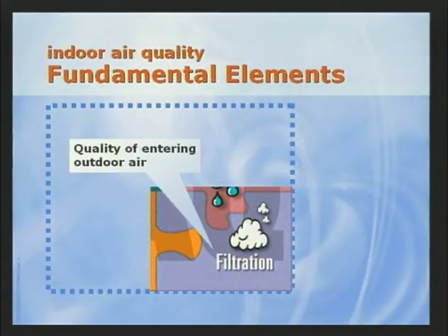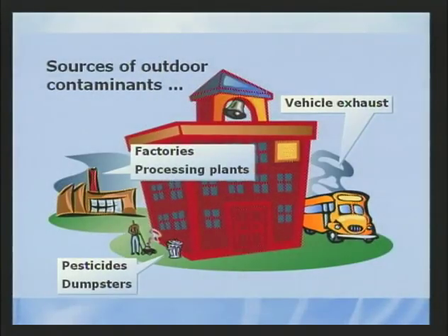Now let's take a moment to look at the ventilation air from the standpoint of how clean it needs to be. The use of outdoor air for ventilation is based on the premise that the outdoor air is cleaner than the indoor air. While that's usually true, there are cases where the air surrounding the building can also be a source of contamination and should be treated before it's used for ventilation air. If the outdoor air in the vicinity of a school is heavy with particulate matter, say from a nearby manufacturing operation, additional filtration may be required. Gaseous pollutants and odors can also be an issue that may need treatment.